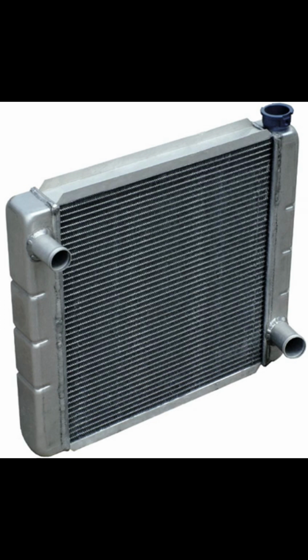Pressurized cooling systems. It is generally a limitation of most cooling systems that the cooling fluid not be allowed to boil, as the need to handle gas in the flow greatly complicates design. For a water-cooled system, this means that the maximum amount of heat transfer is limited by the specific heat capacity of water and the difference in temperature between ambient and 100 degrees Celsius.